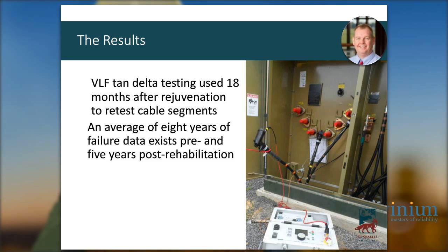Now I've got a pretty good history: 8 years before we started cable injection, and 5 years after we started this aggressive cable replacement plan. The total population of failures is 66 at this point—again, the majority occurred before we started injecting or in the early stages—but we've had only 3 since we started the cable injection and aggressive replacement program.